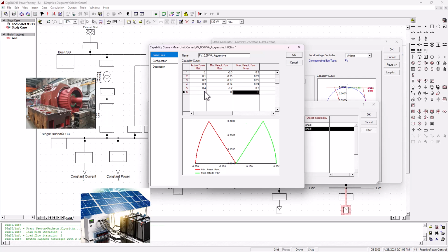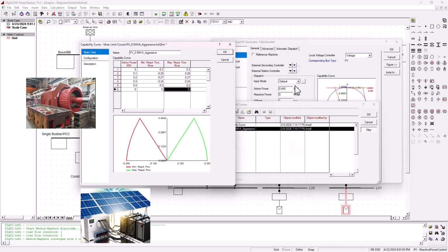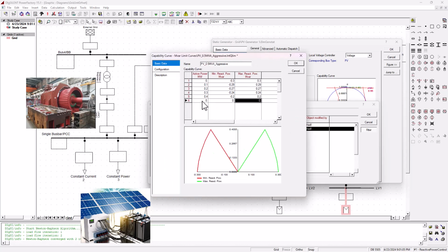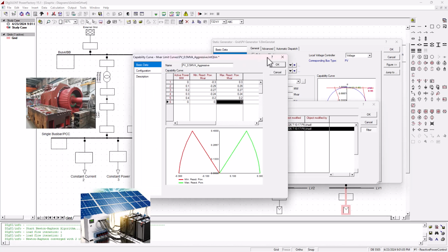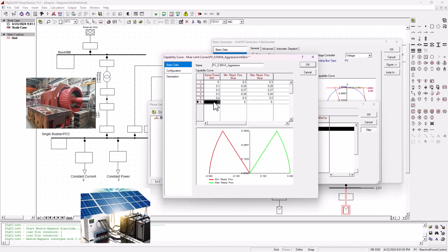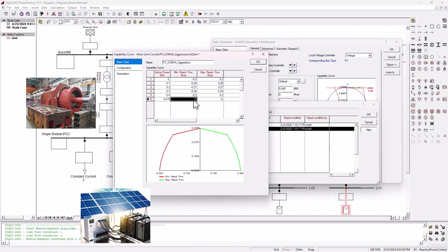Now we're nearing the maximum MVA of this PV generator that we're working on. It's 0.5 MVA, but the active power we can see there is only 0.448. So which means if we supply active power 0.475, which is already the absolute maximum, at this point there is a little bit of room of reactive power, but that can now take us above the MVA rating.